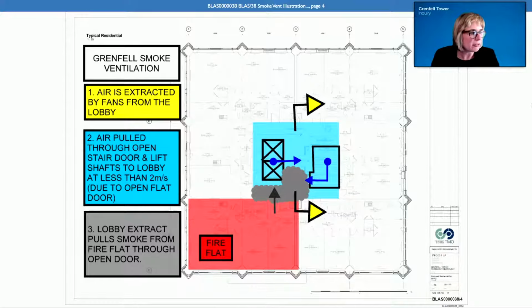Basically, the fire doesn't need this system to make it flow into the corridor - it will naturally do it. So are you saying it will make no difference to the extent of smoke flowing into the lobby, that you've depressurised the lobby by extracting air at both sides? It should actually make conditions better, because you're interrupting the flow. So when the smoke is flowing across the corridor, you're sucking it out. You'd need a very powerful system to actually cause the normal smoke momentum to be pulled further, and you haven't got that powerful a system in this building, I'd suggest.